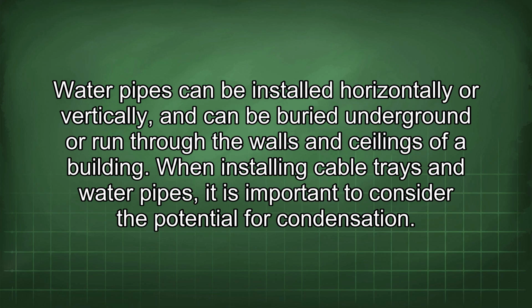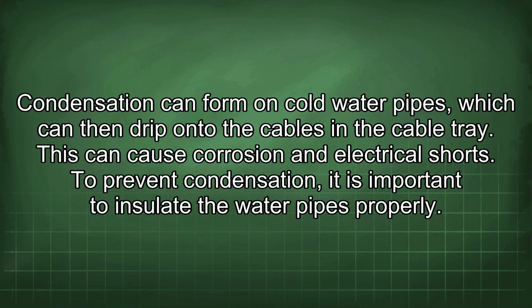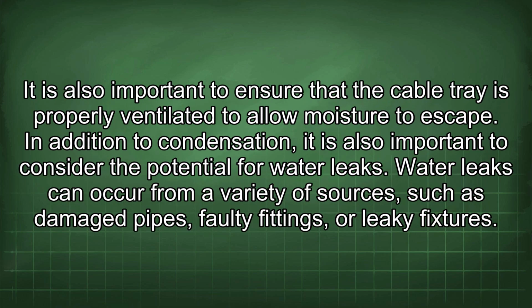When installing cable trays and water pipes, it is important to consider the potential for condensation. Condensation can form on cold water pipes, which can then drip onto the cables in the cable tray. This can cause corrosion and electrical shorts. To prevent condensation, it is important to insulate the water pipes properly. It is also important to ensure that the cable tray is properly ventilated to allow moisture to escape.